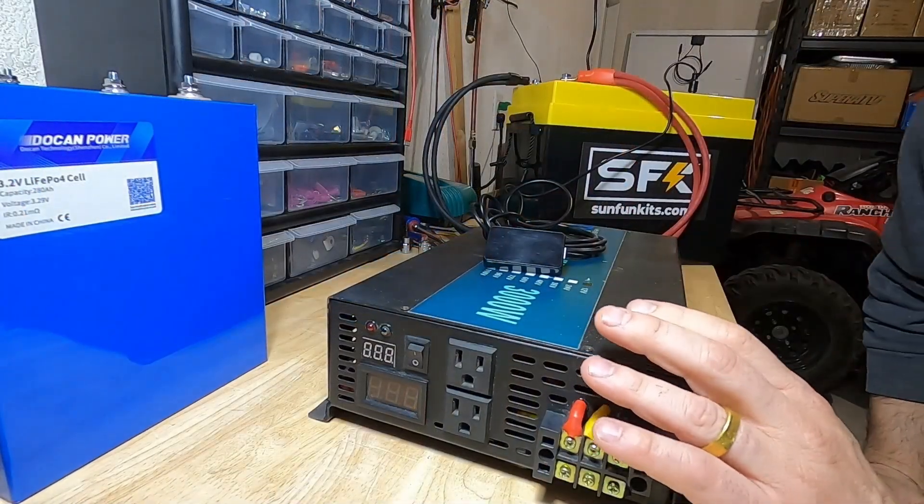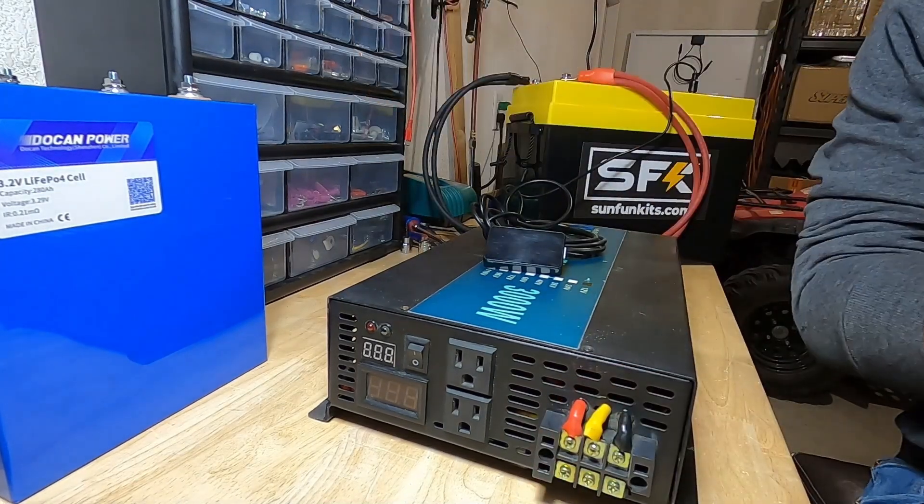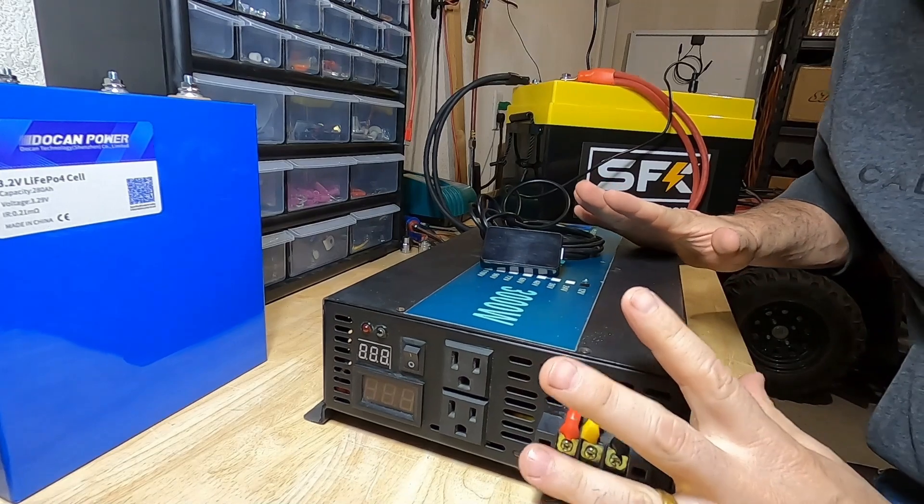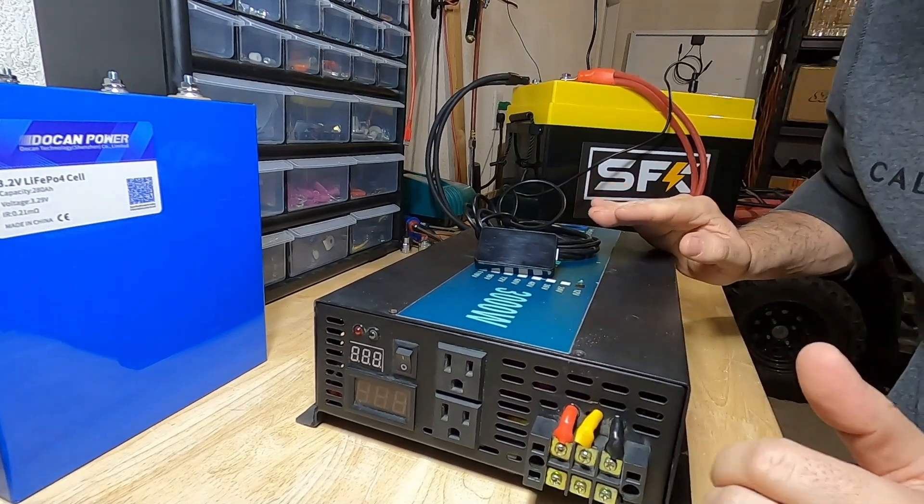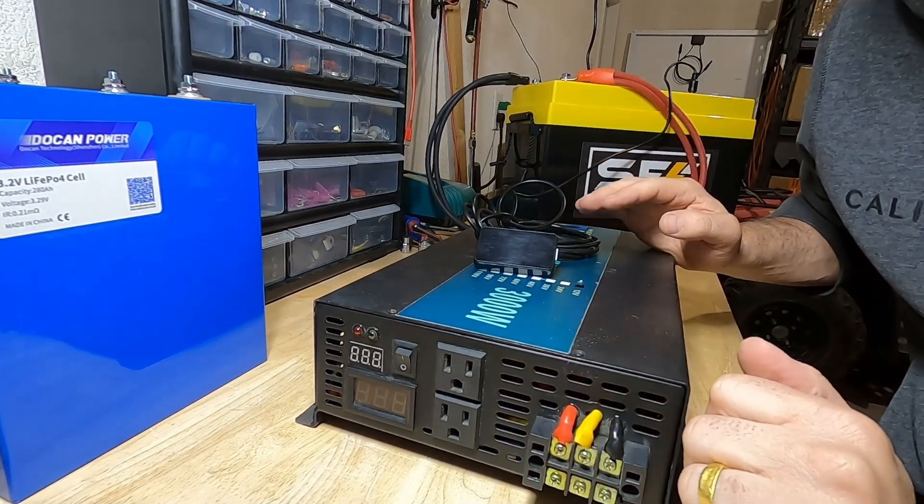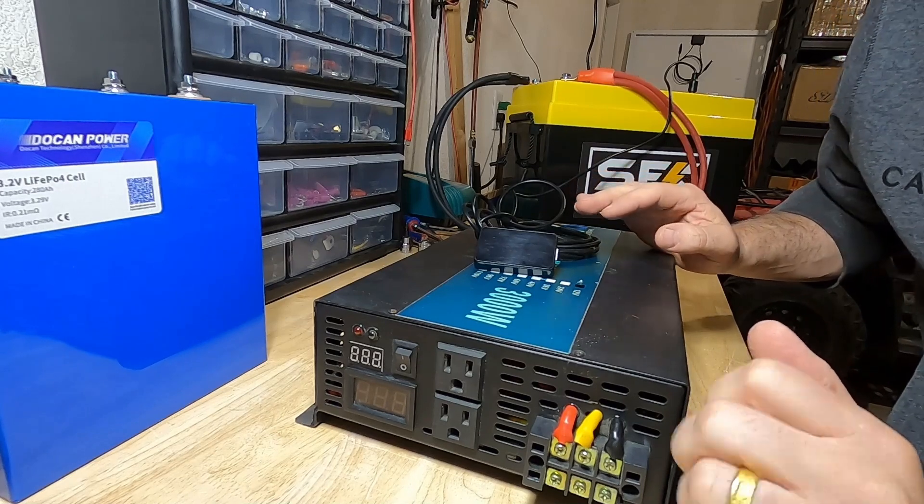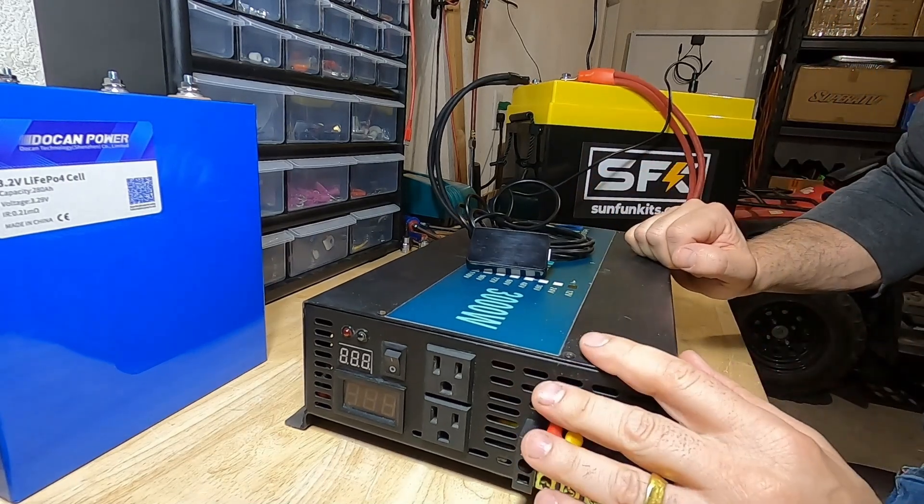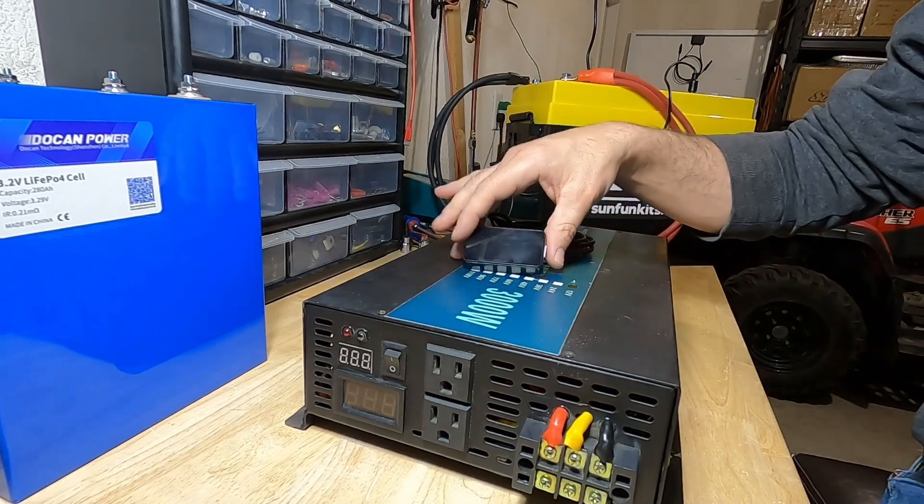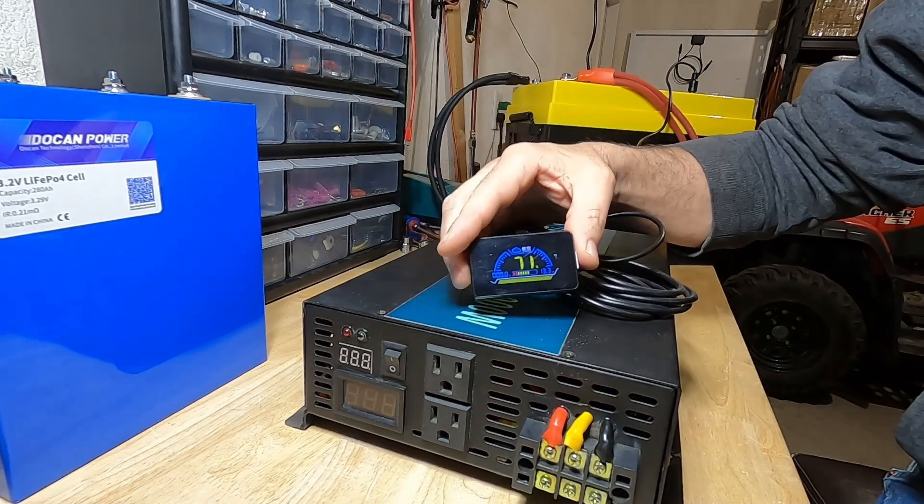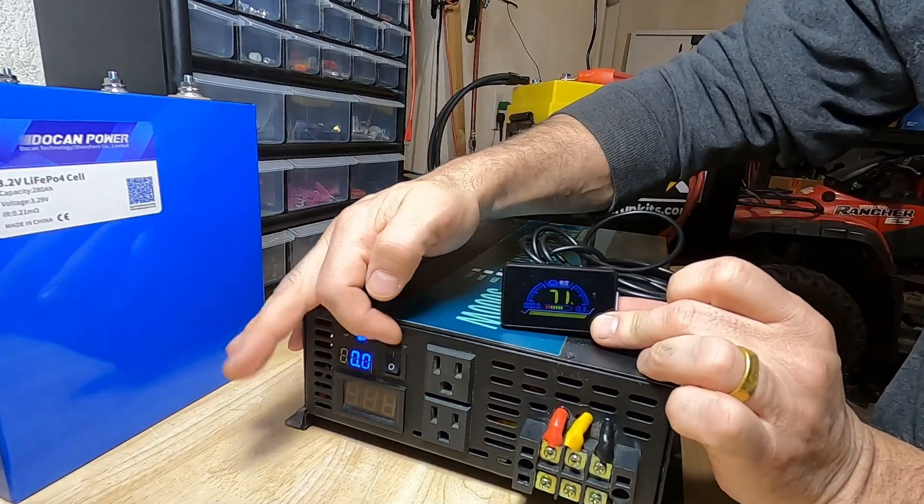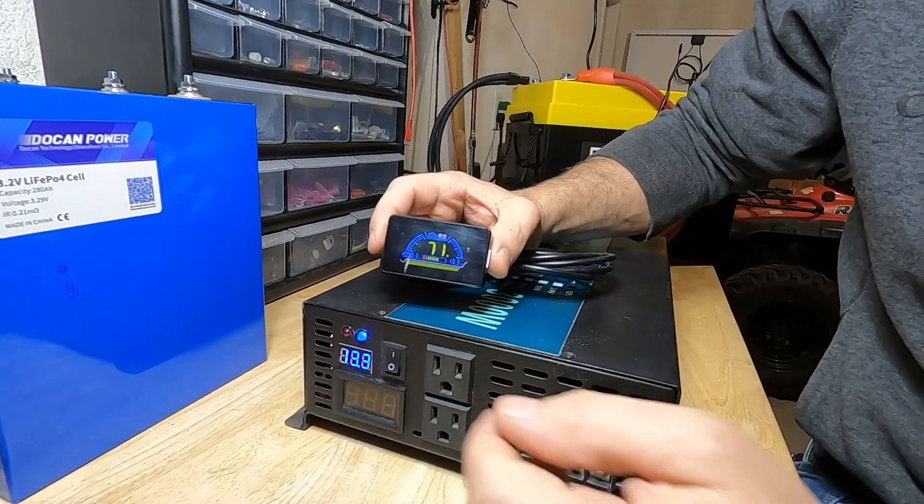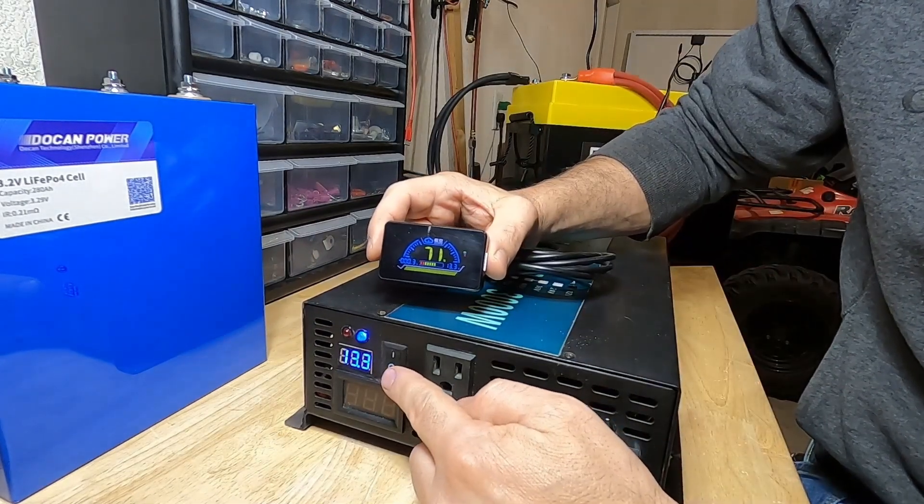Before we take this inverter apart, I want to illustrate the proper way to discharge the inverter. You never want to just go in here blind—the capacitors can hold charge for weeks, months on end, and they can be very dangerous inside.